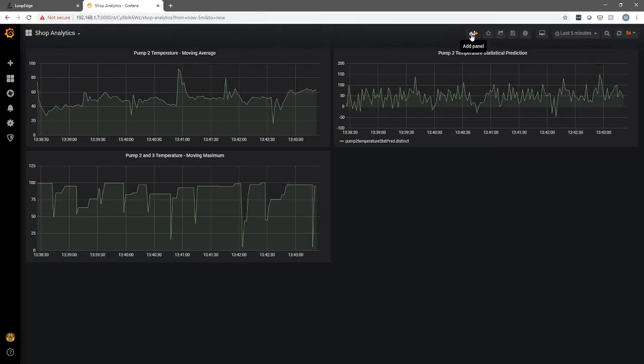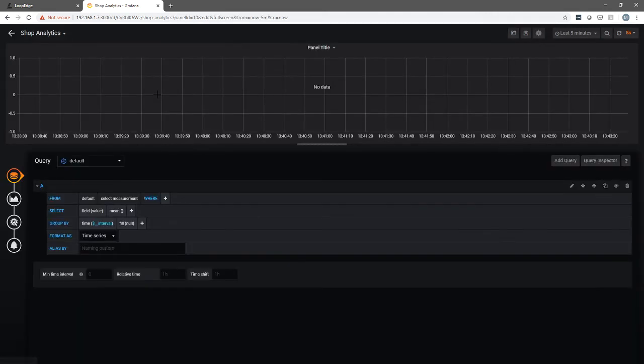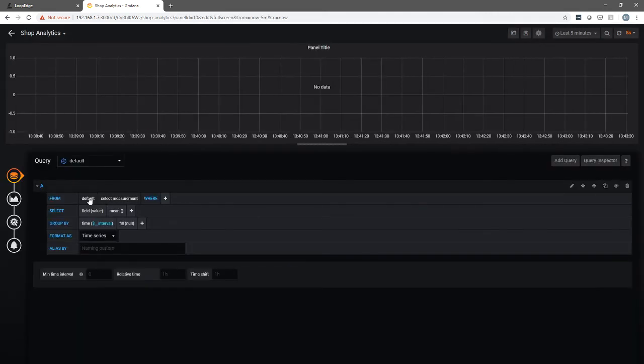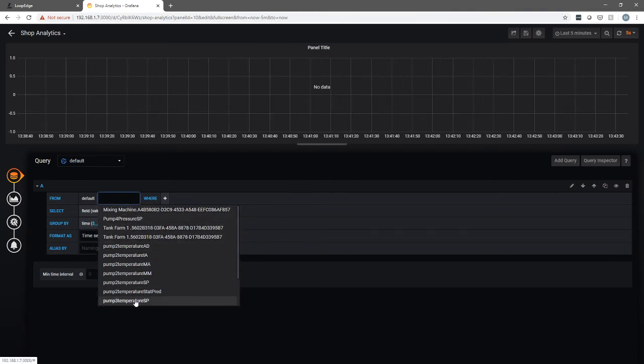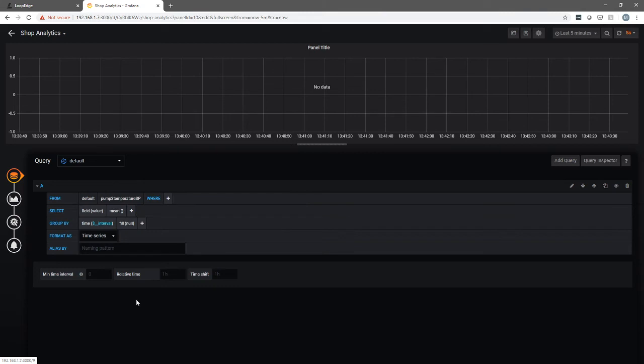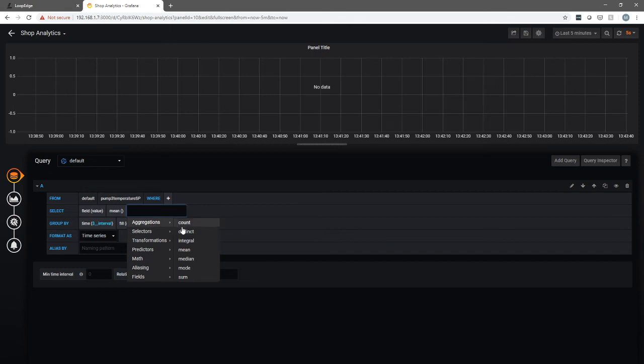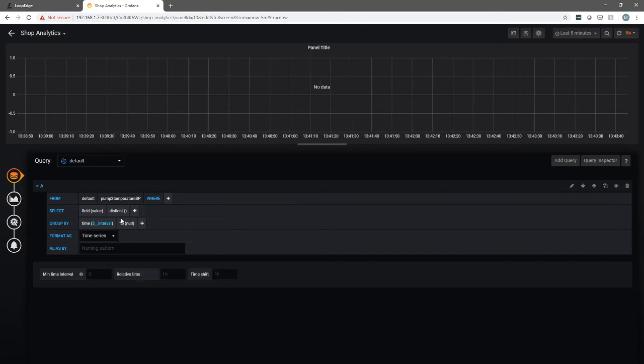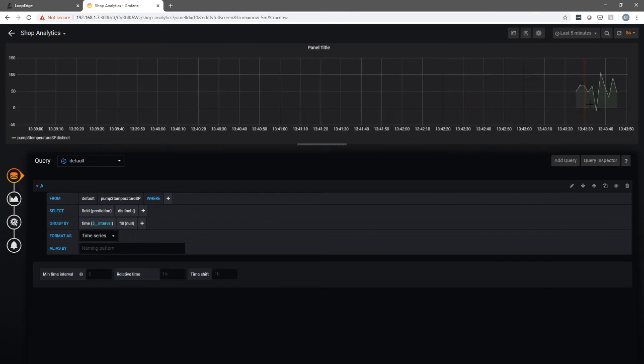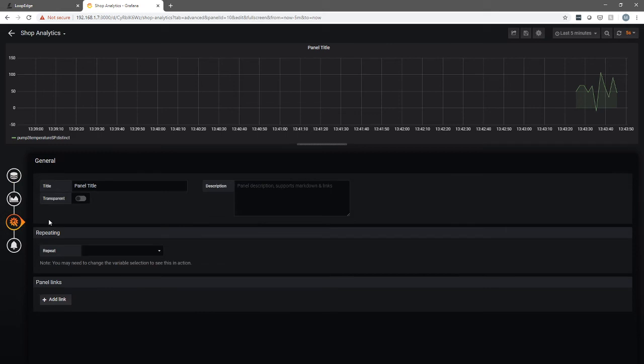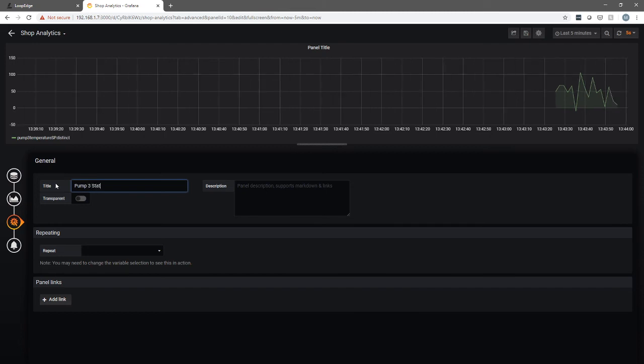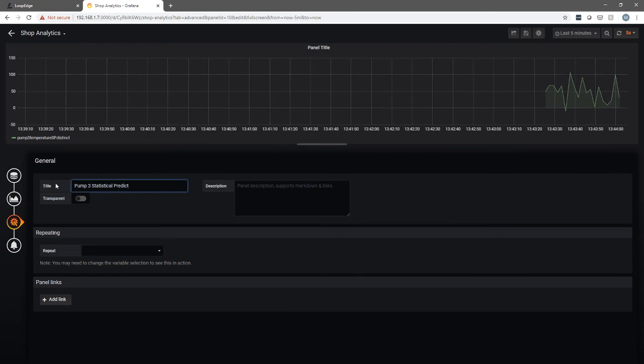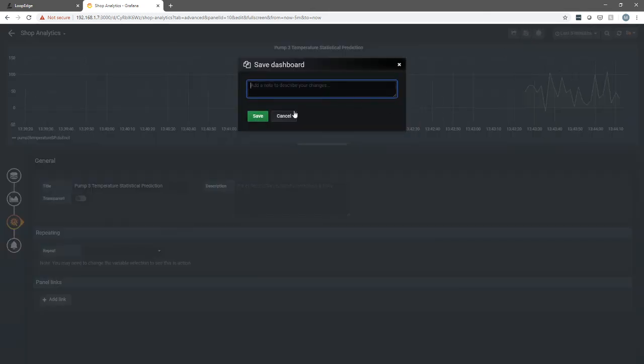So if we go over here we can hit add panel. We'll add a query. We will select from our default database and we will pick pump three temperature SP. That's the one that we just set up. So it's already collecting data. And instead of mean we're just going to change that to distinct. And the value is prediction. You can see already it's starting to show up there. We can add a quick little title that says pump three statistical prediction temperature and we'll save.